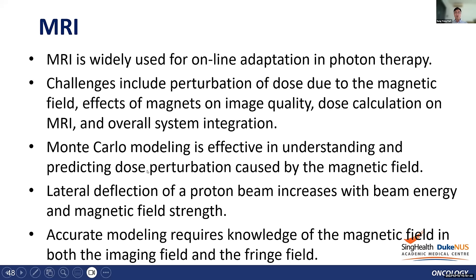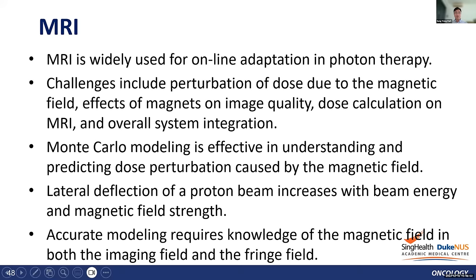Monte Carlo modeling is effective in understanding and predicting dose perturbation caused by the magnetic field. Lateral deflection of the proton beam increases with increasing beam energy and magnetic field strength. Accurate modeling requires knowledge of the magnetic field in both the imaging field and the fringe field.